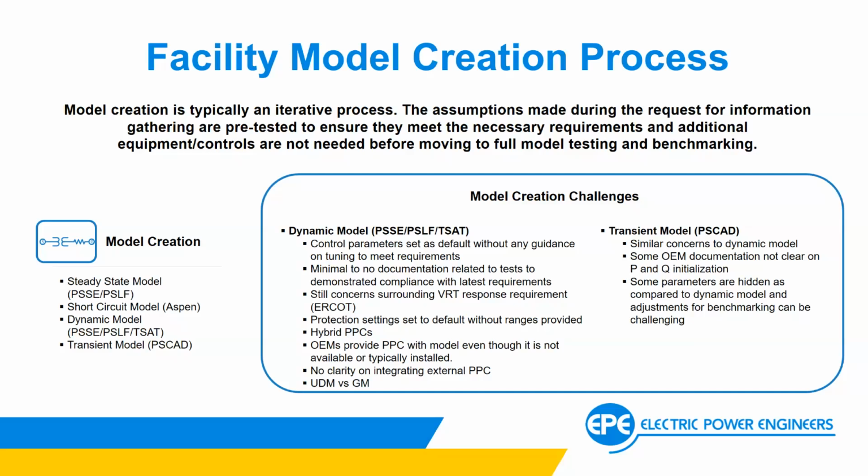Without some special consultant to come in and develop that PPC for them, a decision has to be made: whether you change the inverters to generic and make sure they match the response, or you reach out to a consultant that can develop those PPC controllers and integrate them with the inverters. Some PPC manufacturers have those models. Some integrate with some manufacturers, some don't. So it's a growing concern that we see, especially with the use of more PPCs.